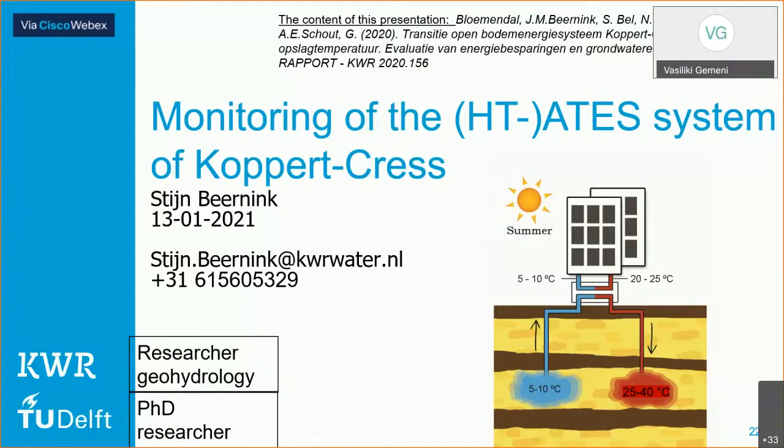Did you observe any problems with fouling at temperature levels of around 40 degrees Celsius? With fouling, with bacterial growth. No, we didn't find it. And that's probably also because those higher temperatures are only sometimes there in the subsurface. For instance, on a daily basis during the hottest part of the day, for instance, during 2 or 3 hours, we can inject this very hot water, but in the evening, we also inject water with a lower temperature. This mixes in the subsurface and the temperature decreases again. So no, we didn't find that, but of course that's of interest.